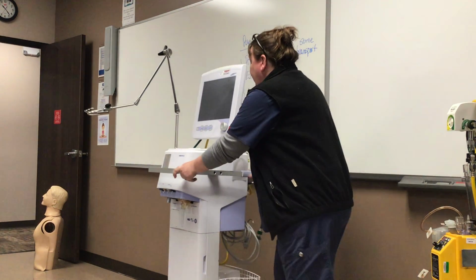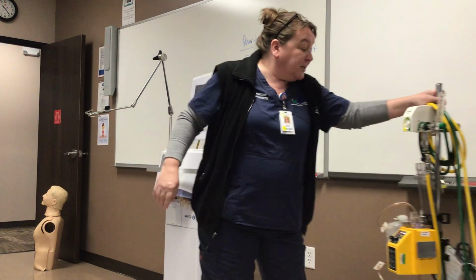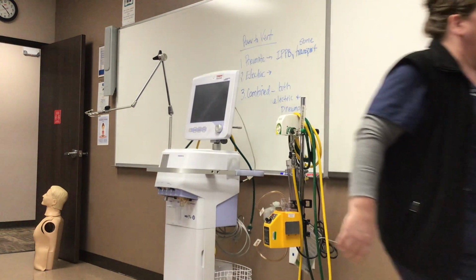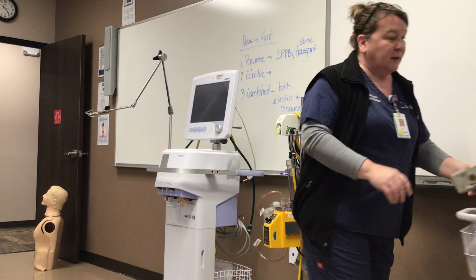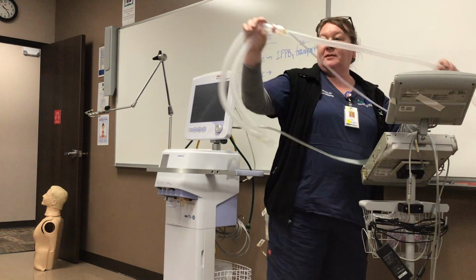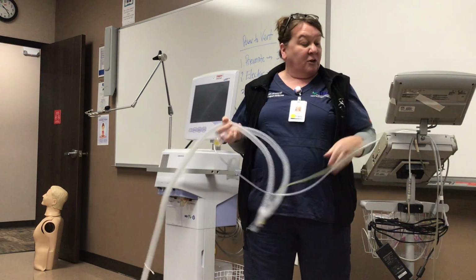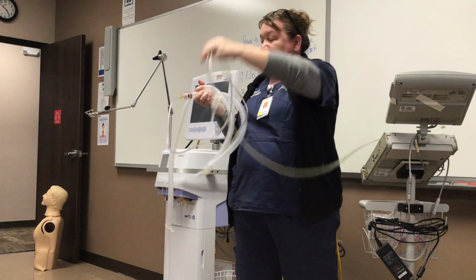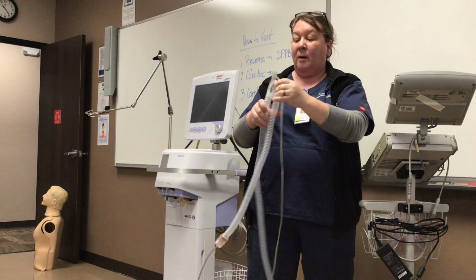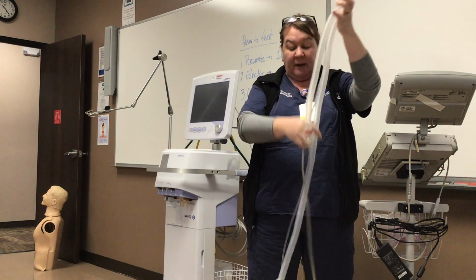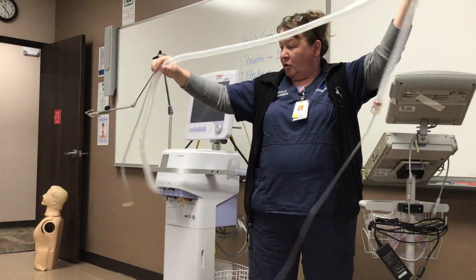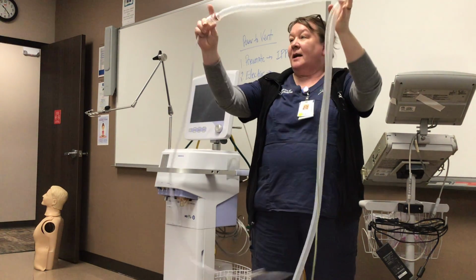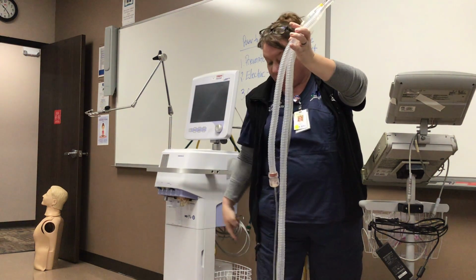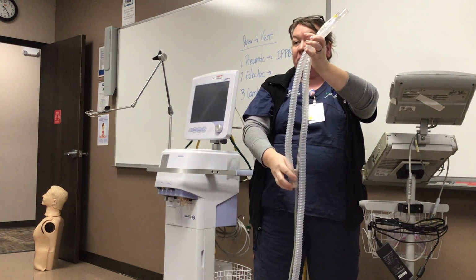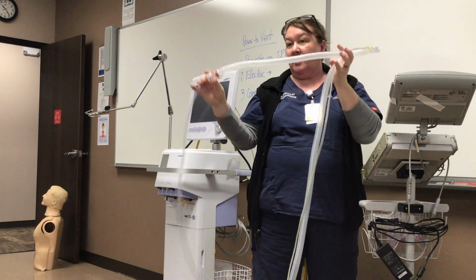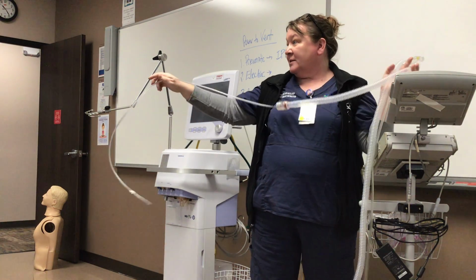So that's where the exhalation valve is on that one. On the LTV, it's actually external. Because you'll note that this circuit is just a single limb for the most part with an extra side. So it's different than the double circuits you see on your regular vents. And this is not uncommon for a transport vent or a home care vent to have just one tube. So this is the exhalation valve on this circuit. The air goes to the patient, and that valve is closed. When the patient exhales, it comes back out and goes through the valve as it opens. And then it just has a pressure line on it.